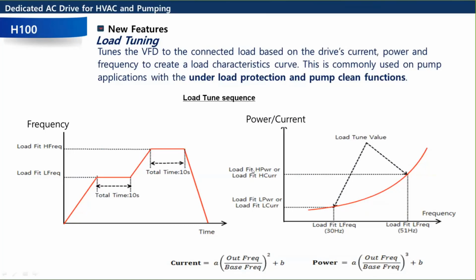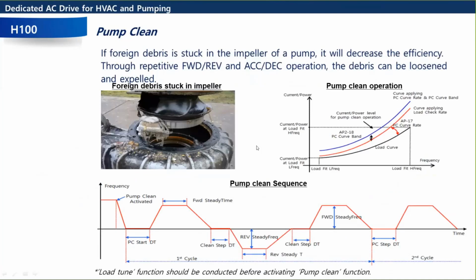So if you do a load tune, which is like a secondary auto tune, then you can do stuff like this. Pump clean. This is a great feature. If you ever get into wastewater, those guys have a function called deragging or something like that. That's what a pump clean is, or anti-jam. So if there's anything stuck in the impeller, we could detect that. We could do it automatically, or we could do it with a switch, and we could have the drive rock forward and backward until we get rid of that solid or that debris that's jammed up in the pump.